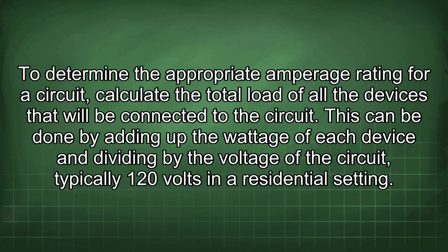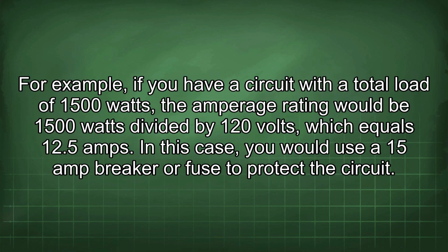This can be done by adding up the wattage of each device and dividing by the voltage of the circuit, typically 120 volts in a residential setting. For example, if you have a circuit with a total load of 1500 watts, the amperage rating would be 1500 watts divided by 120 volts, which equals 12.5 amps. In this case, you would use a 15 amp breaker or fuse to protect the circuit.